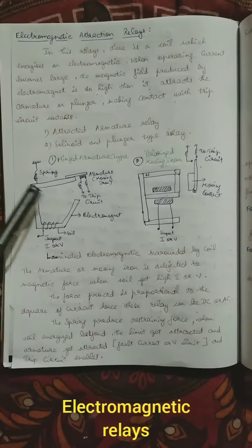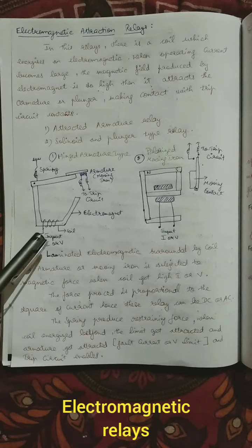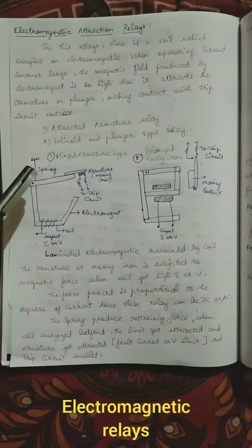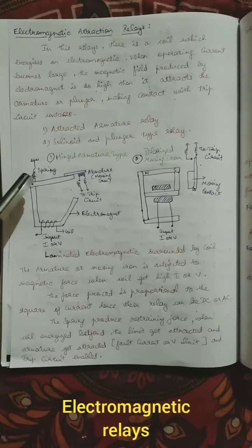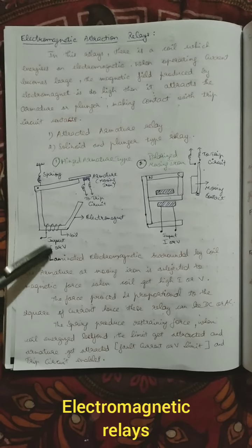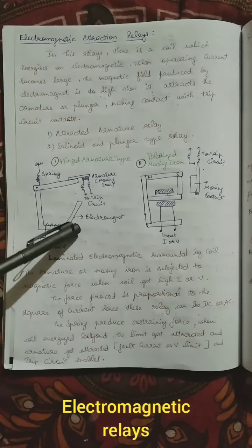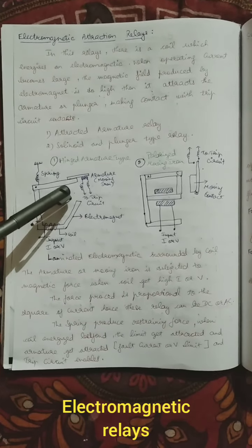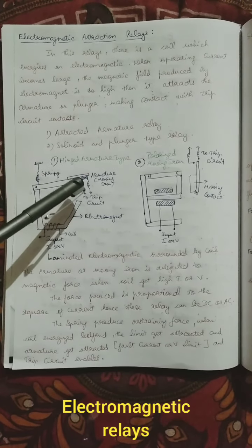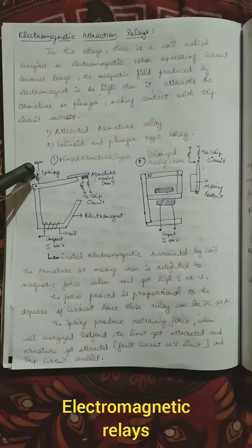For the hinged armature type, this is your magnet surrounded by a coil. The coil input is AC or DC current or voltage. A spring is connected to the top of the magnet which produces a restraining force. When the fault current occurs, the coil gets energized and produces an electromagnetic force. This electromagnetic force must be higher than the restraining force for the armature iron particles to get attracted and move.